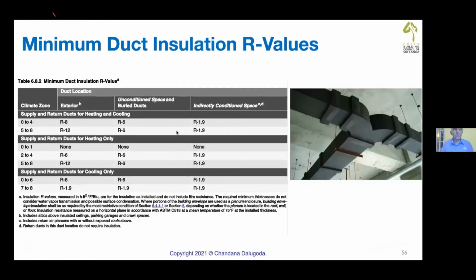Similarly, thermal insulation. You can't just use thermal insulation. You'll have to calculate the thermal insulation thickness as economical thickness to prevent condensation. But once you do the calculation, you'll have to find the R value. So these are the R values we are supposed to keep for climate zone 0. Exterior R8, buried ducts R6, indirectly conditioned space 1.9 or 2, something like that. Piping, similarly, you have R values.